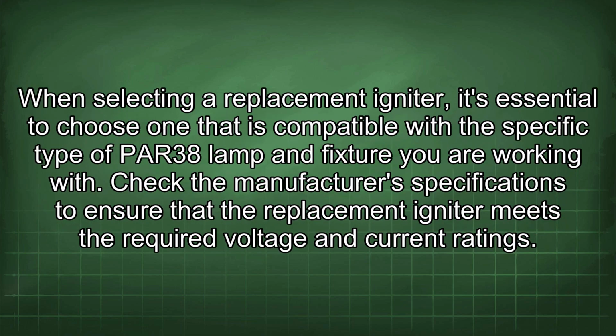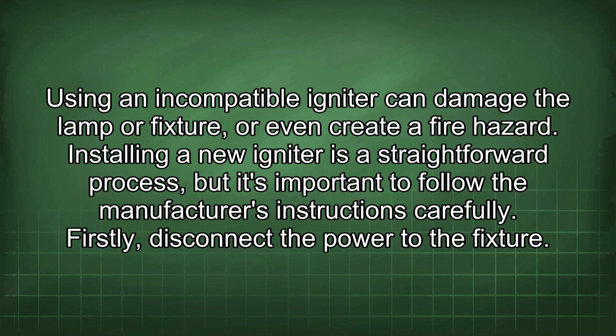When selecting a replacement igniter, it's essential to choose one that is compatible with the specific type of PAR38 lamp and fixture you are working with. Check the manufacturer's specifications to ensure that the replacement igniter meets the required voltage and current ratings. Using an incompatible igniter can damage the lamp or fixture, or even create a fire hazard.